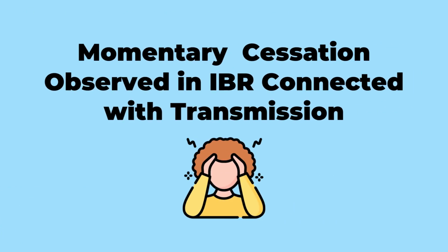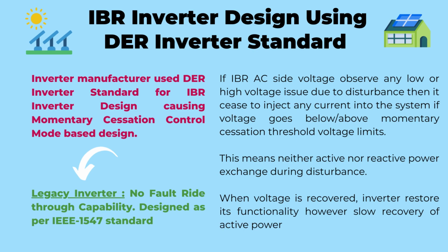Interestingly, this momentary cessation control mode and trip function, originally designed for a distribution system connected DER to ensure safety, have also been observed in many inverter-based resources or IBR plants connected at the transmission level, where it was not required. This has posed a significant challenge. In the past, there was no specific standard for large solar and wind power plants connected to the transmission grid by inverter-based technology. Inverter manufacturers used the DER inverter standard for IBR inverter design, which resulted in momentary cessation control mode being implemented.